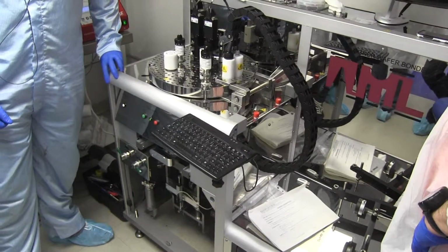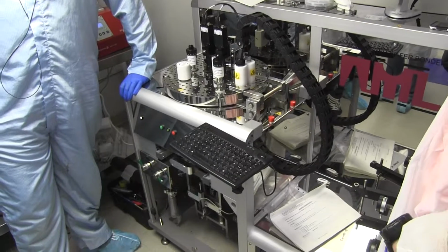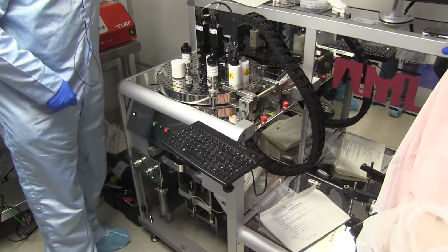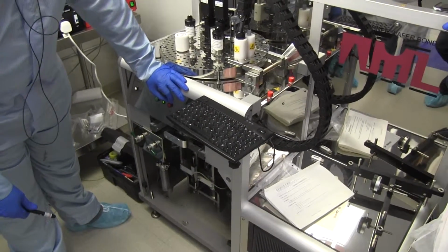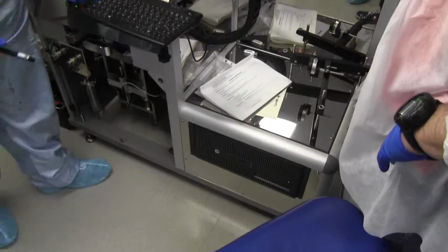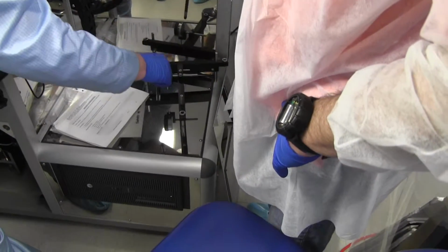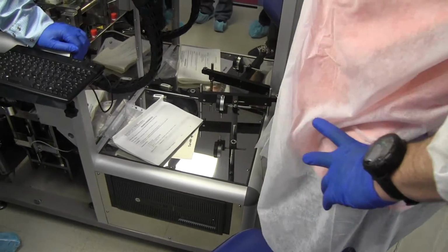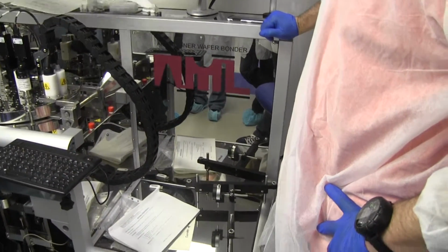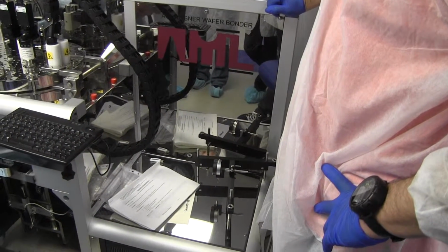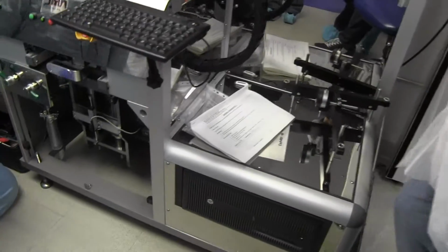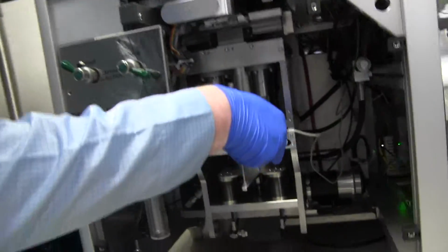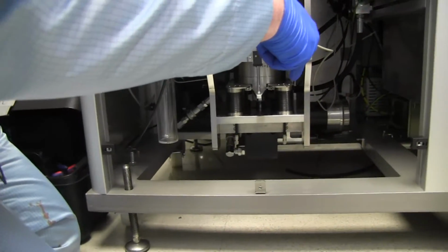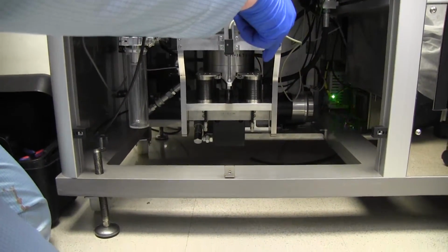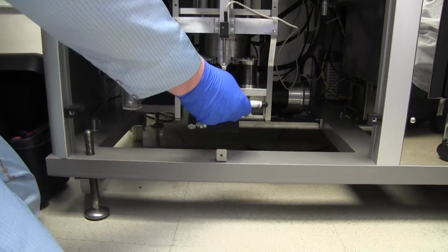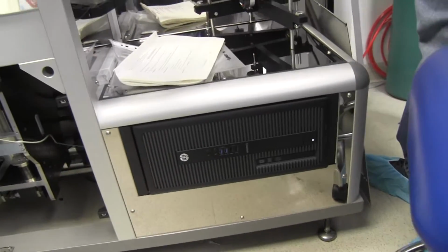Where's the power supply? Which power supply? The 500 volts. Okay, there are two high voltage power supplies. They are not really accessible, but one of them is located underneath the PC here, which is for the plasma system, and one of them is mounted on a sort of rail system that way. You can just see the edge of that gridded box. That's the high voltage supply for the bonding voltage. That power supply can deliver 2,500 volts, and the one for the plasma system, which is underneath at the back there, can do 500 volts.